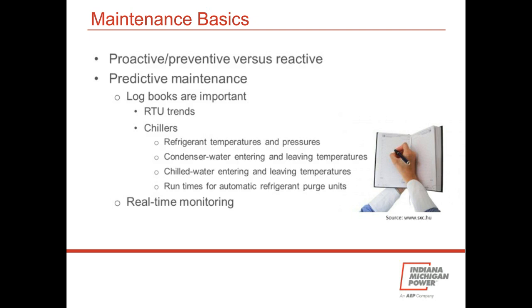In that case, it's good to use log books to track some critical predetermined operational metrics, things like condenser coil cleanliness, condenser fan operation, refrigerant charge levels, etc. In addition to that, real-time monitoring has contributed greatly to the ability to review and respond to changes in your chiller or rooftop operation and overall process performance. When you do that, operators can compare, say, past baseline results against current readings to determine if there's a problem that might be cropping up in the future.